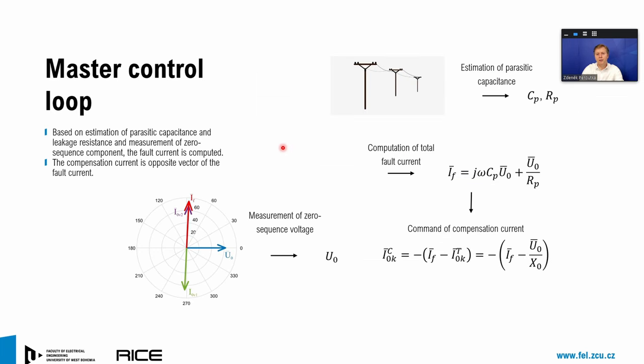How is the compensation current generated? We do the online estimation of the parasitic capacitance and parasitic resistance of the grid, as I explained, using the pseudo-direct impulse. And we measure the zero sequence voltage. With these known parameters, we are able to calculate the fault current, having the reactive part and the active part. The fault current is partially compensated by the transformer. This current can be calculated from the zero sequence impedance of the transformer and the known zero sequence voltage. When we subtract the compensation current generated by the transformer from the total fault current, we get the command for the generation of the compensation current by our converter.